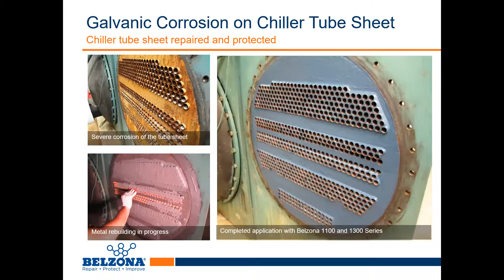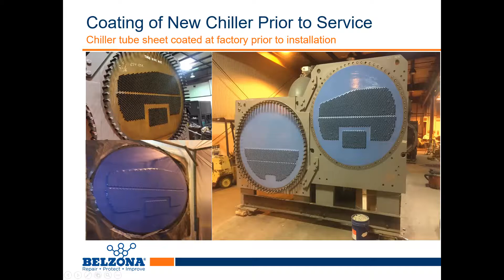So in this next slide, we can see, this is a good example. This is a chiller tube sheet that was suffering from corrosion due to galvanic corrosion. The surface was prepared again by grit blasting, washed with Belzona 911 to remove all residual blasting debris. The tubes were plugged, as we mentioned, with corks. And Belzona 1111, a pretty popular product of ours, was applied to the area using this applicator. The 2-coat Belzona system with 1321 was also applied. This offers protection against the effects of erosion and corrosion, and it's going to have outstanding resistance to any kind of chemical attack.